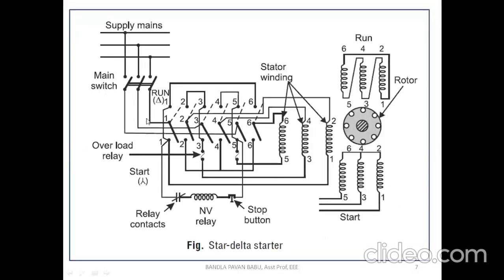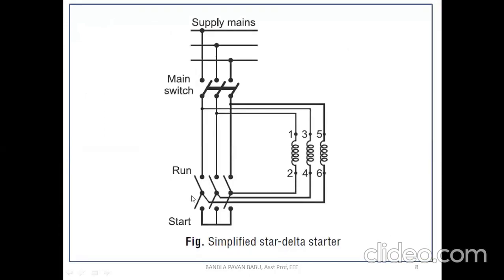So this is the supply mains, and this is the main switch. This may be an MCB also. Look at the tappings here. First of all, see the simplified diagram here. This is the knife switch. Based upon our action, it will be tapped at these terminals or these terminals. If you want to connect the star connection, see here the start position. Start means it should be in star connection. At the starting we are going to connect in star fashion.